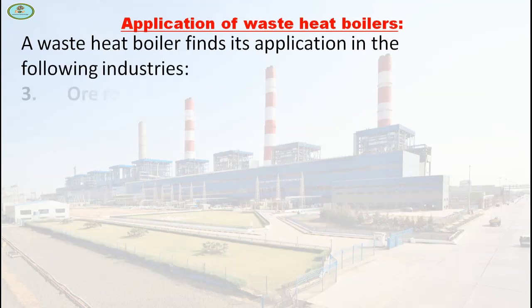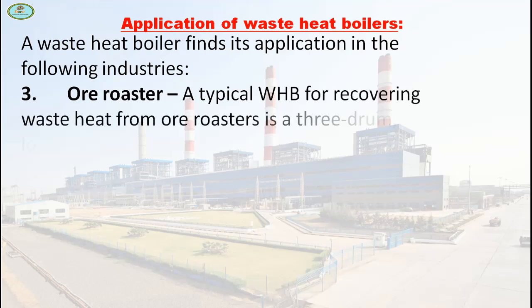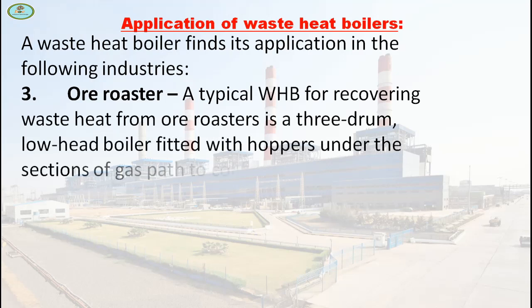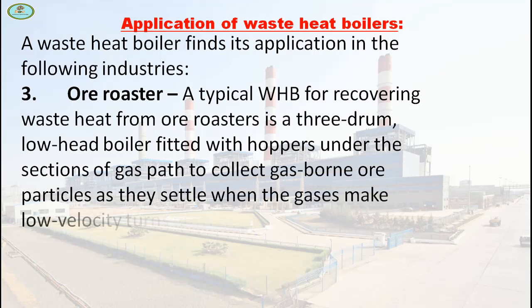Next is ore roaster. A typical WHB for recovering waste heat from ore roasters is a three-drum low-head boiler fitted with hoppers under the gas path to collect gas-borne ore particles, as they settle when the gases make low-velocity turns around the baffles.